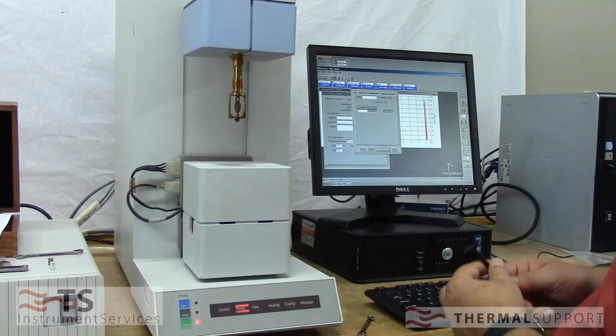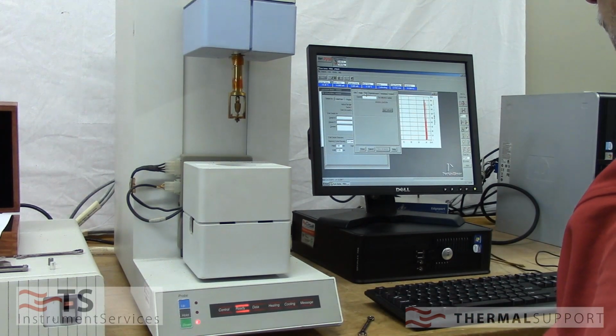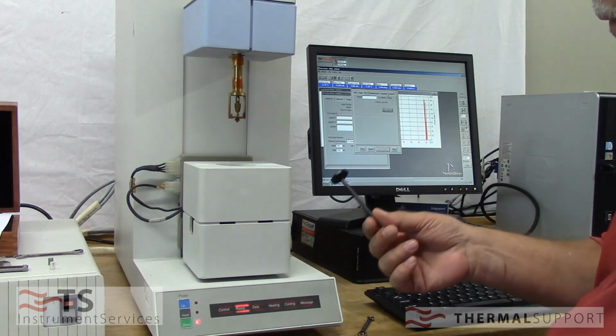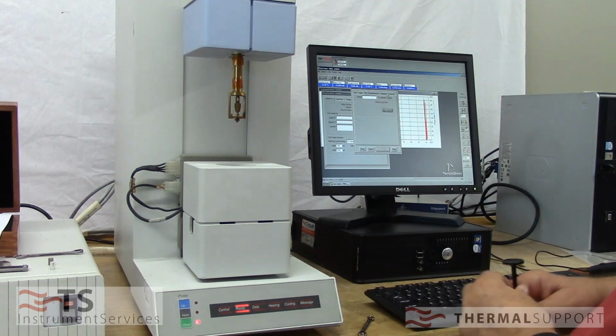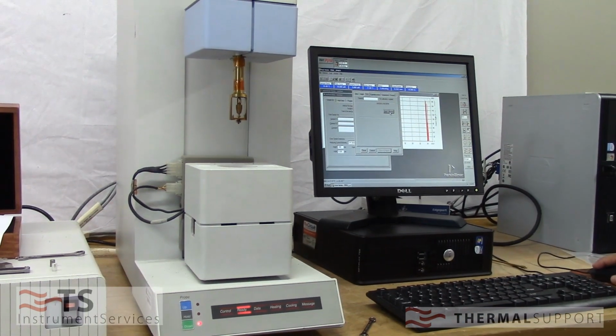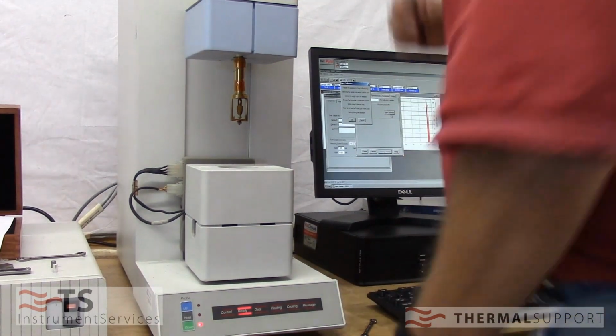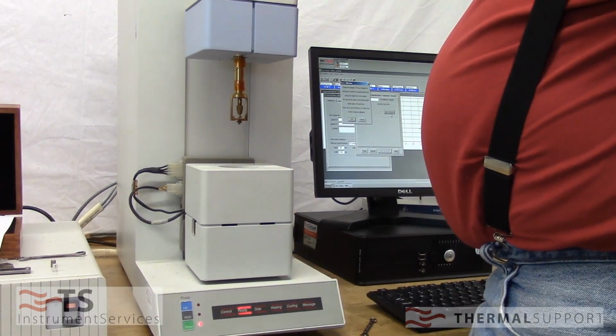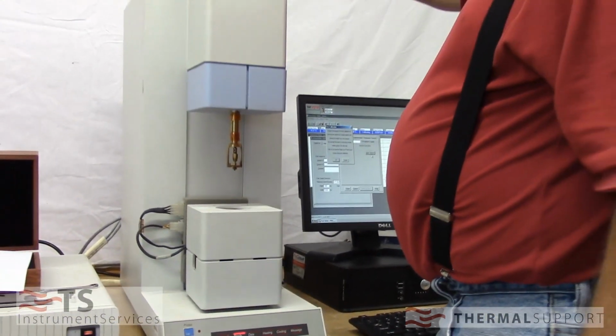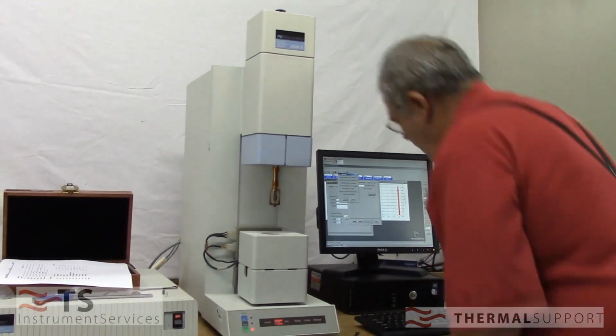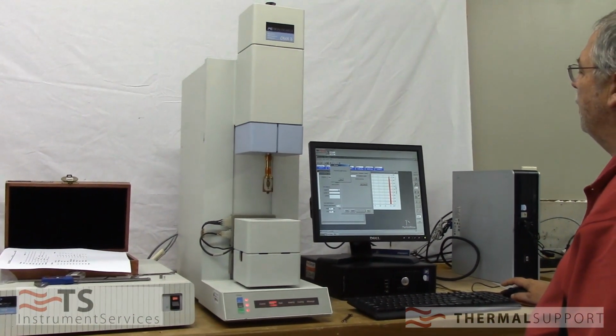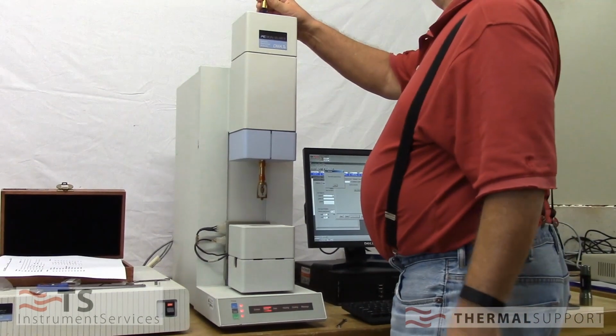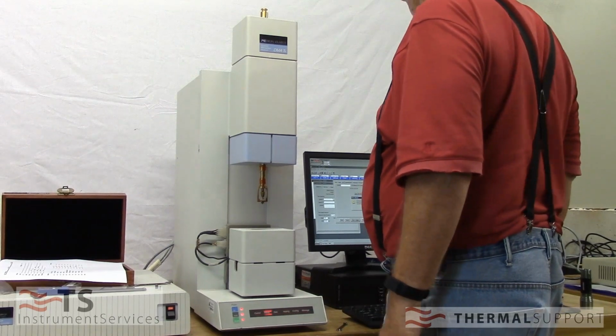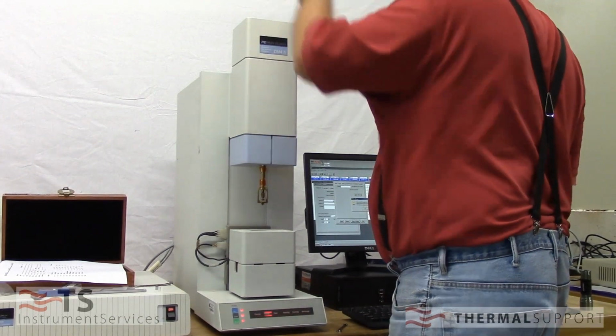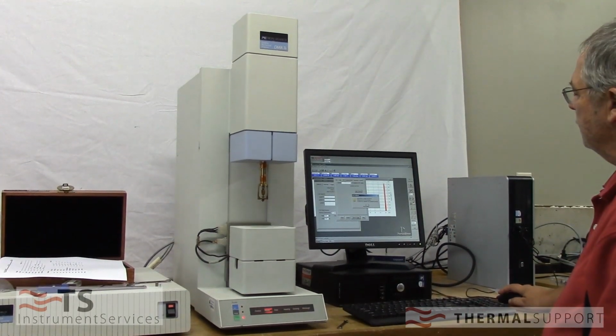Now, if we're going to put a sinusoidal force on here, it's going to be a pretty good idea if we know how much force we're going to be putting on here. So we have a platform, we have a 50-gram weight. We're going to say begin cal. It's going to tell us to put the platform up here, which is going to sit on top of the core rod. We're going to say OK. Now it's going to say put the 50-gram weight on top. DMA calibration has been completed successfully. So we're going to say OK.